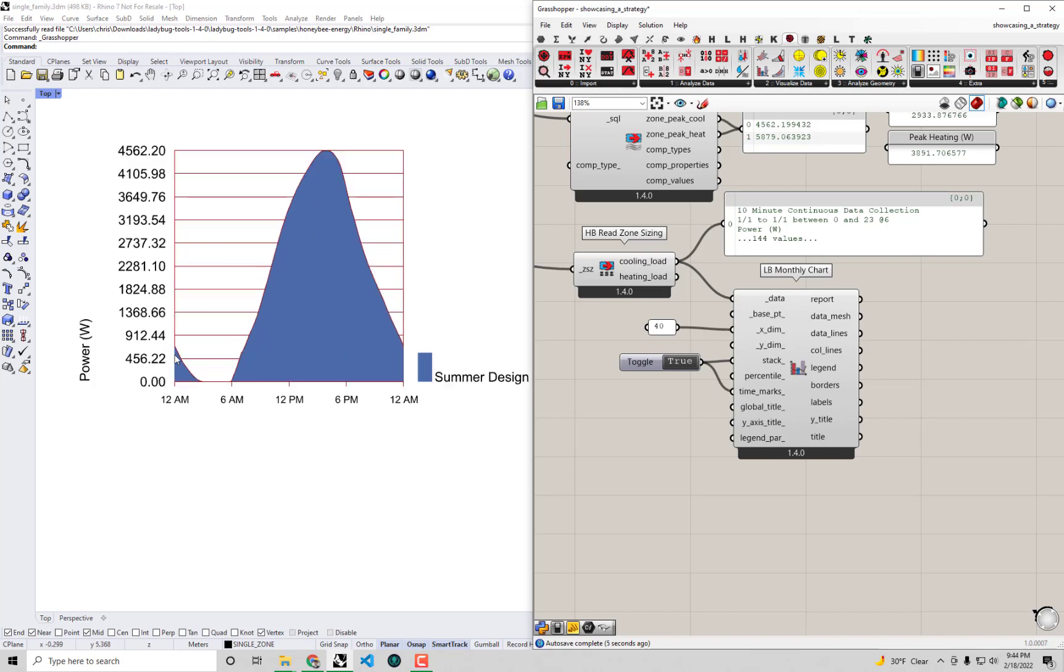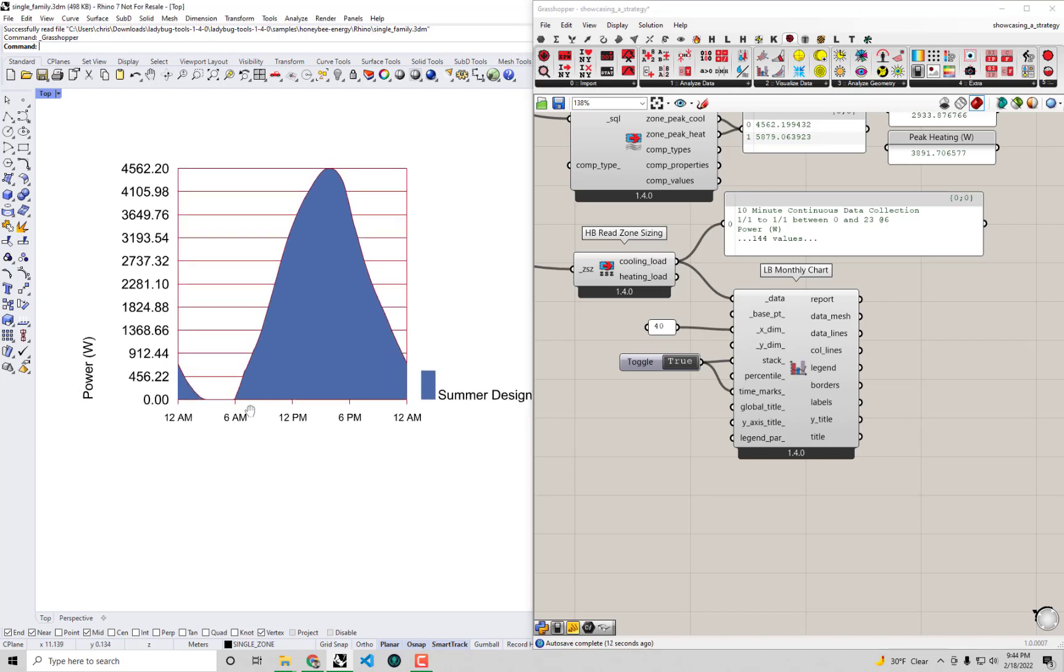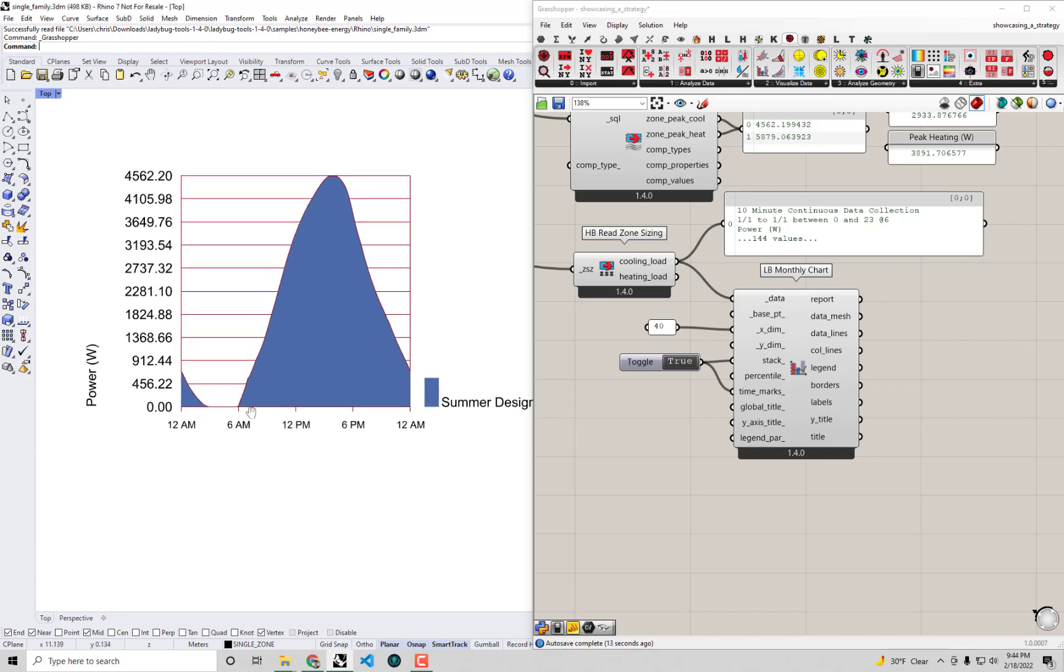This is already looking a lot clearer. We can see at midnight we still have a little cooling, but that drops to practically zero in the nighttime in this LA climate. Probably that's a big result of the diurnal swings we have in the hot and dry climate like in Los Angeles. Understandably, we have the largest peak sometime around 4 or 5 p.m. in the afternoon when the biggest amount of peak cooling is needed over the course of this design day.